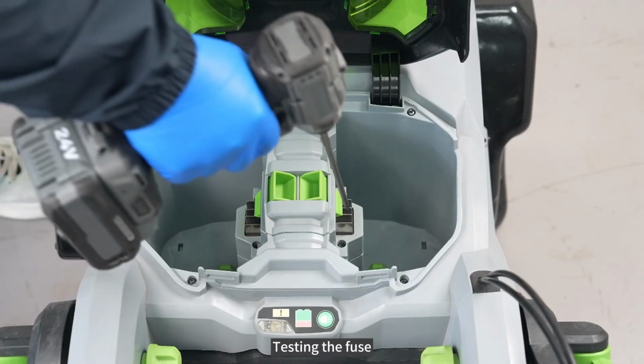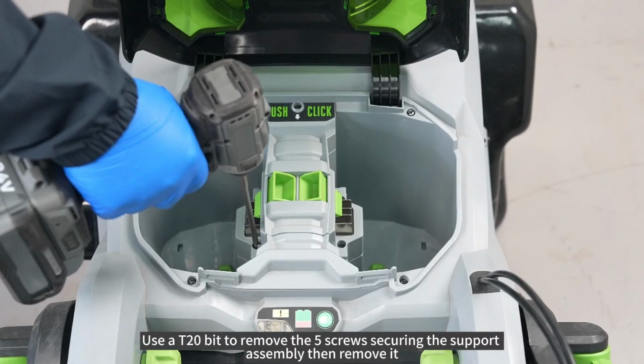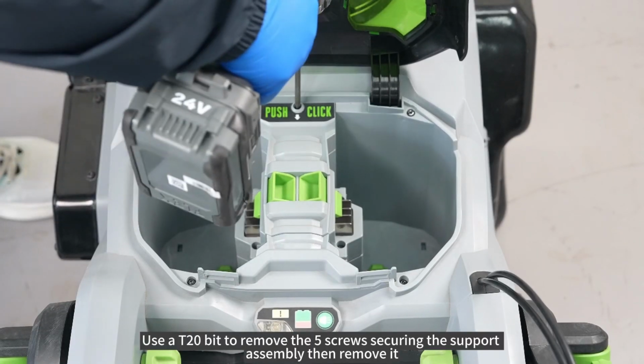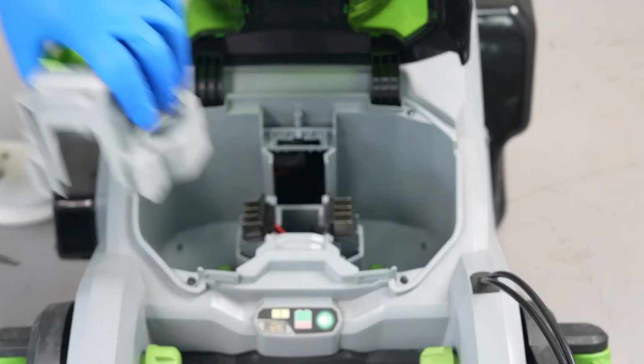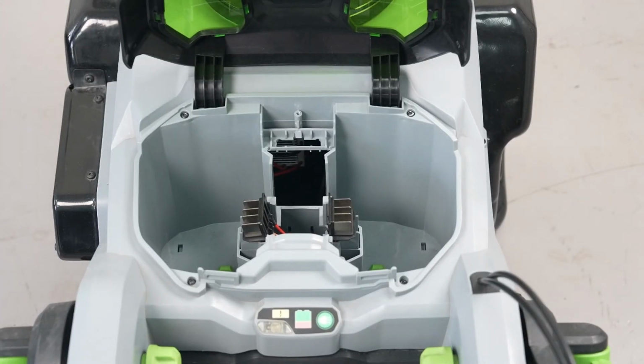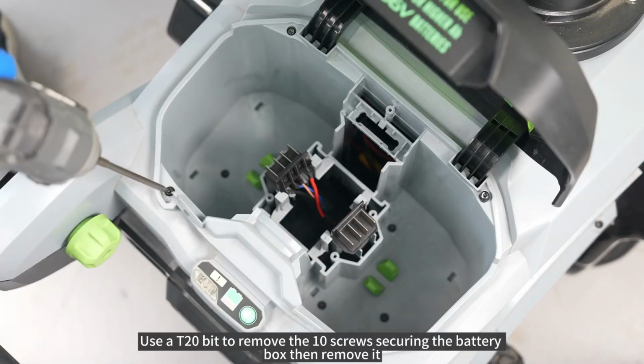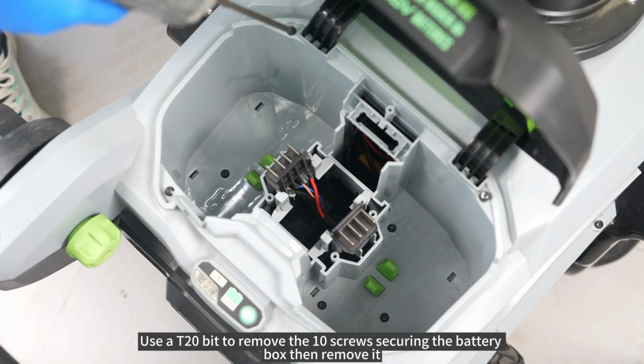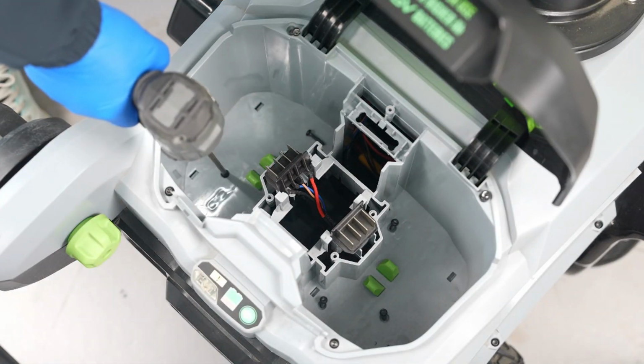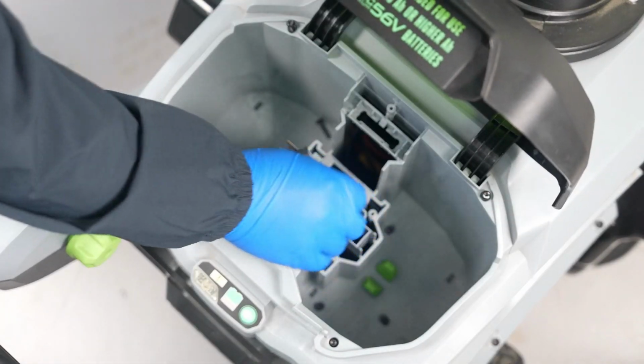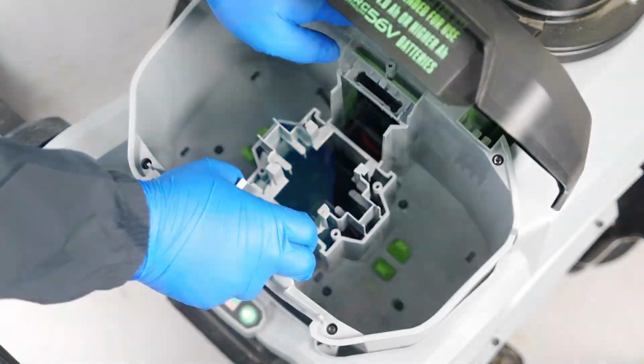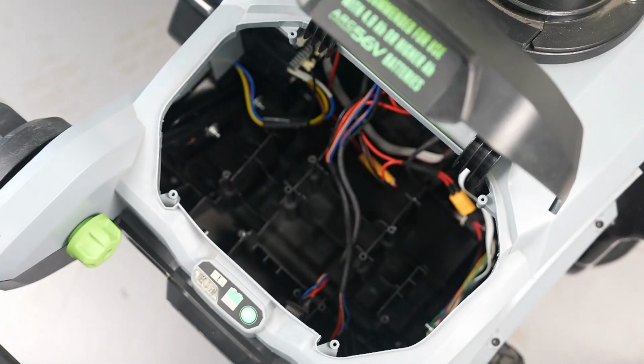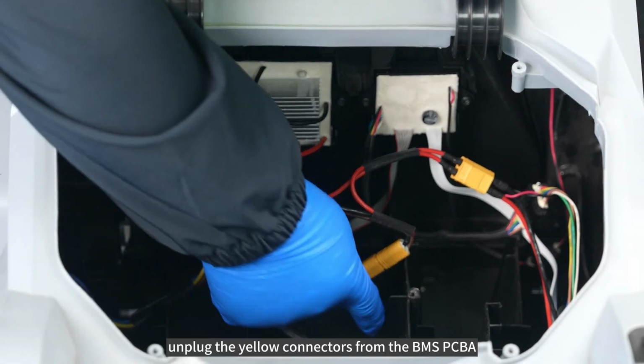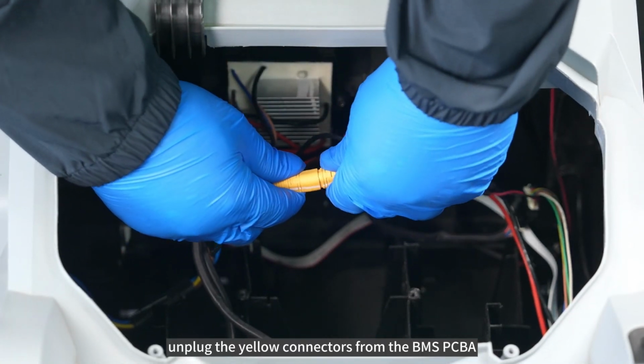Testing the fuse. Use a T20 bit to remove the 5 screws securing the support assembly, then remove it. Use a T20 bit to remove the 10 screws securing the battery box, then remove it. To troubleshoot the fuse, unplug the yellow connectors from the BMS PCBA.